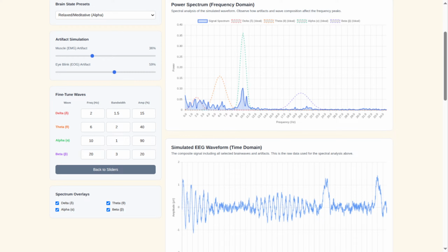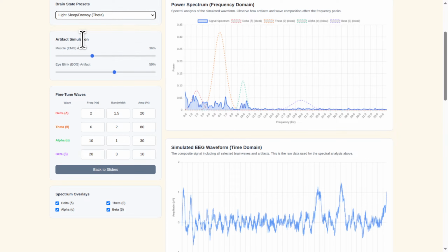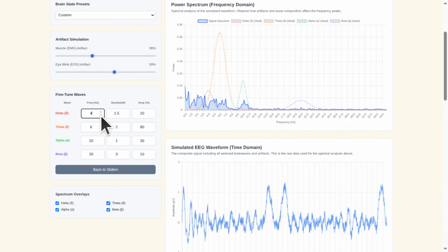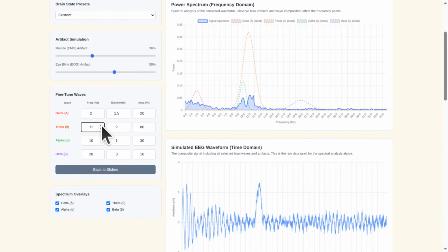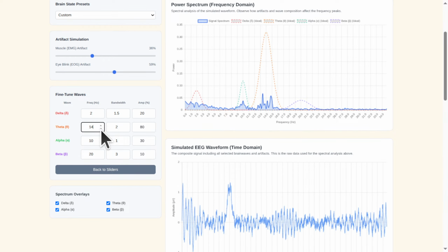So the more realistic path, the one the sources really push for, is about transparency and education. It boils down to a few key things. One, clinicians absolutely need to report the specific recording and processing settings they use. Like, show your work, every time. Put it in the report. Exactly. Two, clinicians need to really understand how these filters and processing steps work, get fluent in the basics of signal processing. And three, always, always critically consider the source. Ask, what machine was this? What settings were used? How might that skew what I'm seeing right now?